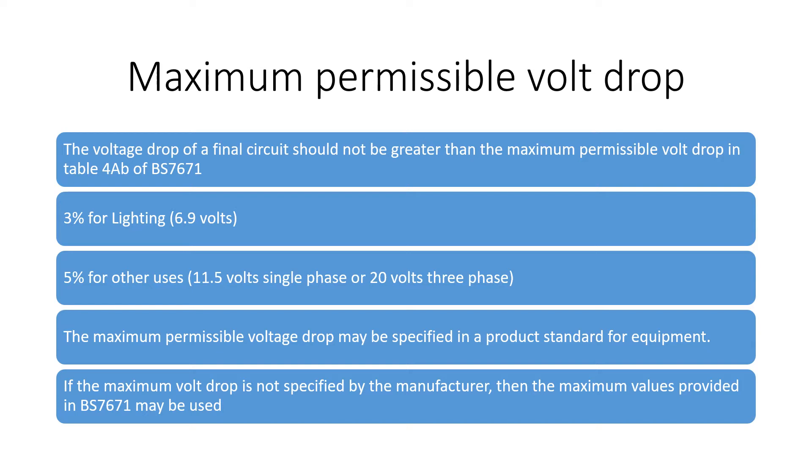I should also mention that Table 4AB specifies higher values for volt drop where low voltage installations are supplied from a private supply, for example where a large installation is supplied from a client's own transformer. However, the final circuit volt drop should still be within 3% and 5% respectively. So for the purposes of this example I'm going to assume that the electricity is supplied from a low voltage public supply.